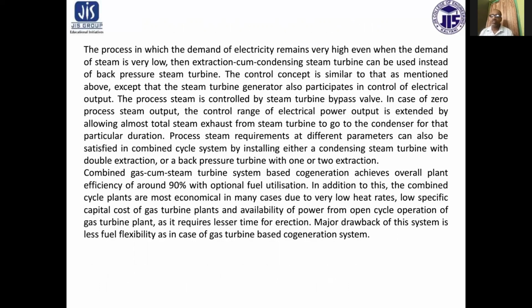The control concept is similar to that mentioned above, except that the steam turbine generator also participates in control of electrical output. The process steam is controlled by the steam turbine bypass valve. In case of zero process steam output, the control range of electric power output is extended by allowing almost total steam exhaust from the steam turbine to go to the condenser for that particular duration.